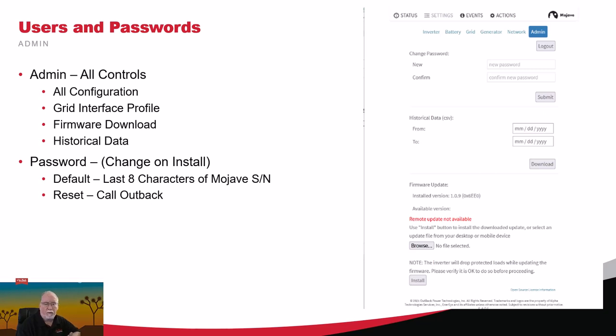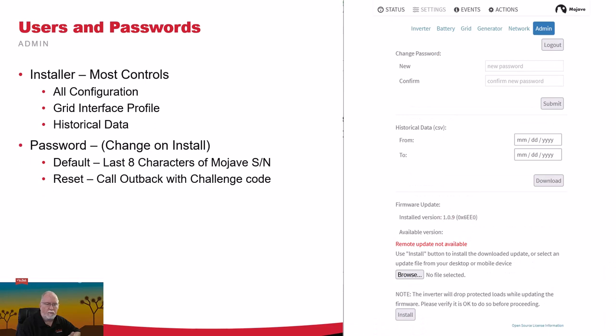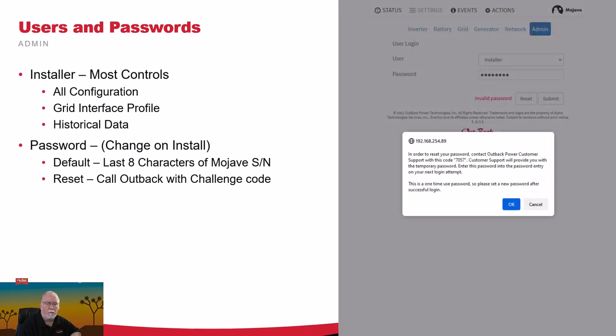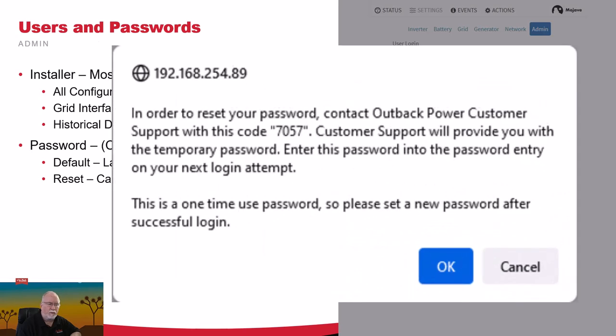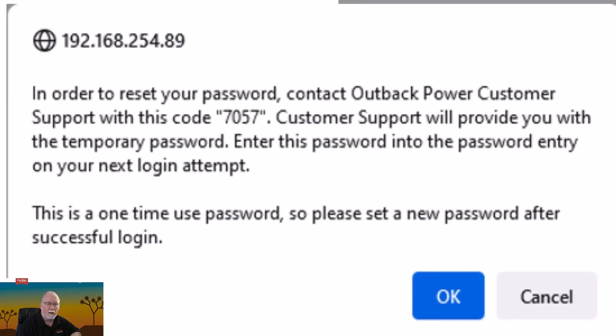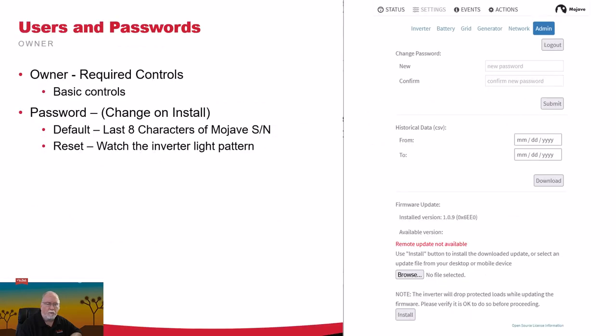Now, again, admin gives all controls, all configuration, grid interface profile, firmware downloads. Password will be the last 8 characters. Change that on default. If you need to reset it, call us. For installer, it gives most of the controls, including the grid interface tab, historical information. Again, the default is the last 8 characters of the Mojave serial number, but the reset is done a lot like the way that our traditional inverters did the reset. Effectively, just send a message to Outback Power, supply the code that is shown on the web page, and then they'll supply you a temporary password.